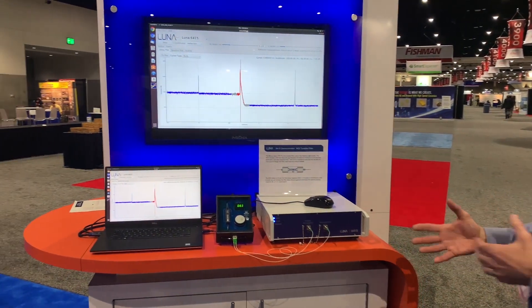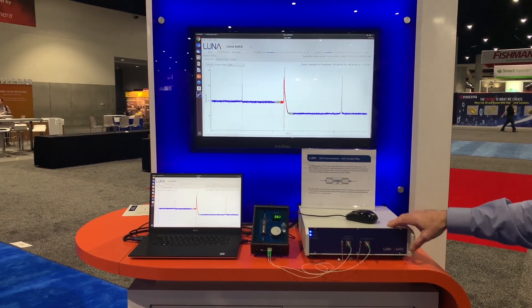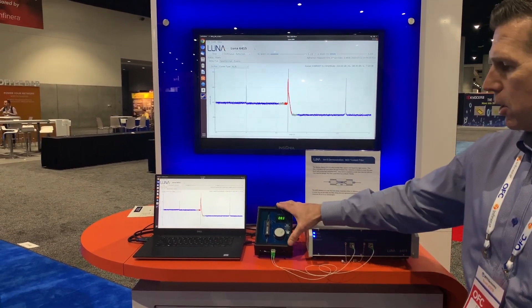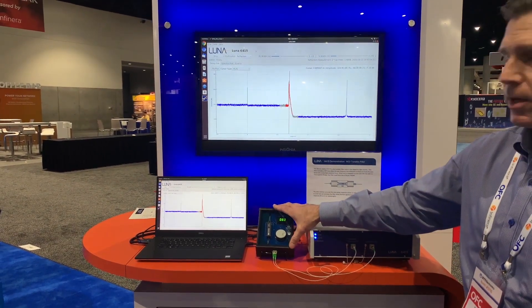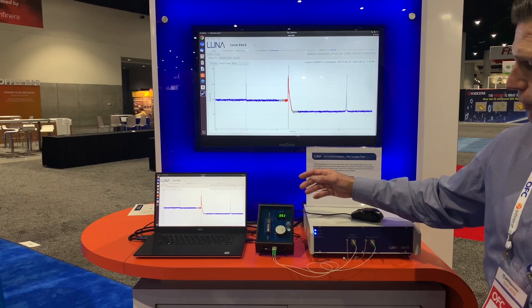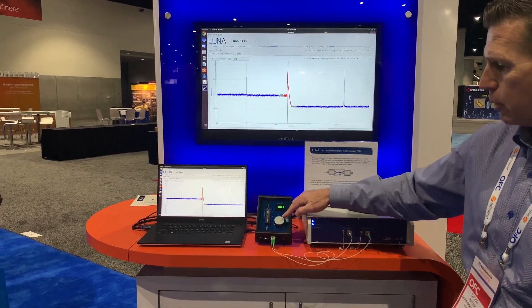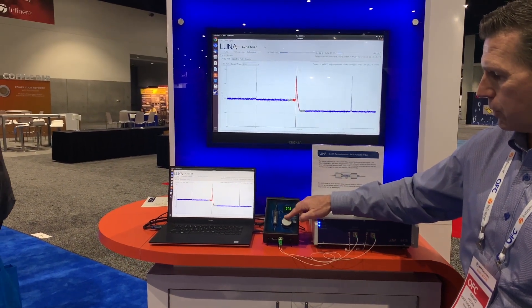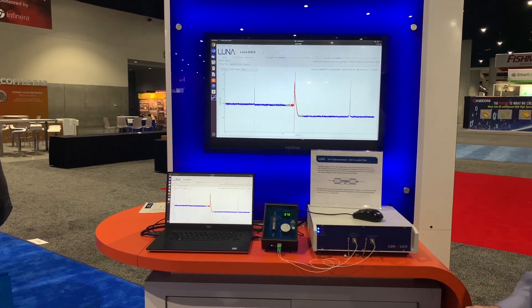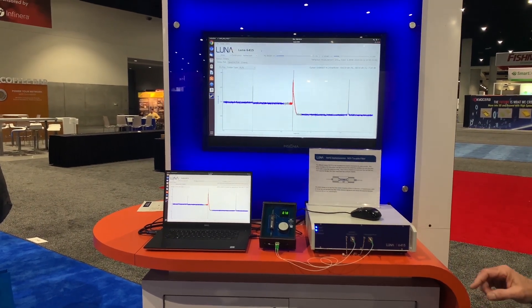In our demo today we have the 6415 testing the response and loss of a LUNA Micron Optics tunable filter that we have set up in this demo box. This is a tunable filter set up so we can easily change the wavelength.